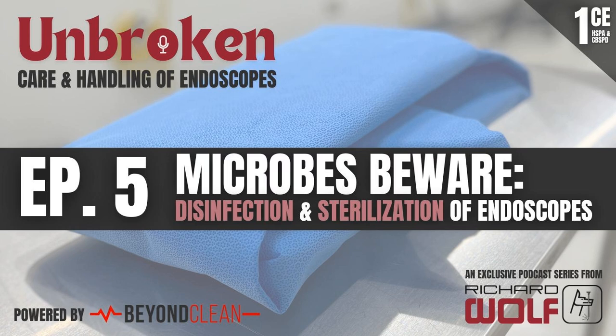Sure. Yeah, I'm going to hit the hot button right away and make a statement. Just because a device is validated for a certain process or method does not always make it the best process for the device. So with that being said, I've seen manufacturers validate low temperature sterilization, for instance, over steam. And then the manufacturer has come out with letters stating that low temperature can only withstand 60 cycles because the epoxies or the components of the device will break down and deteriorate over time.